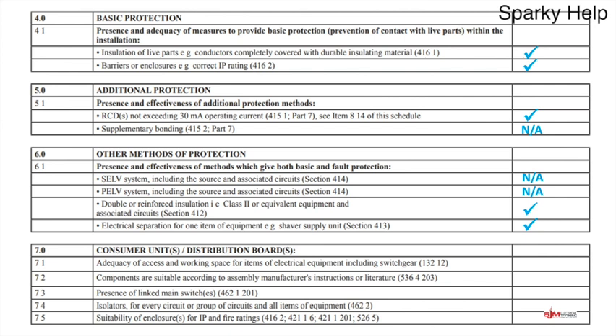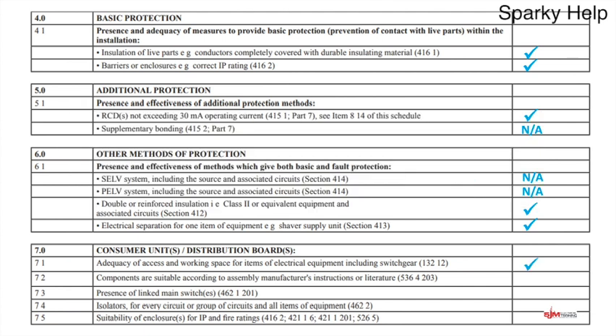The next one, we're looking at consumer units and distribution boards, adequacy of access and workspace for items of electrical equipment including switchgear. The regulations basically just say that wherever you put something you must have sufficient space for the initial installation and later replacement of individual items of electrical equipment, accessibility for operation, inspection, testing, fault detection, maintenance and repair. There are no measurements, you've just got to meet that. So you use your judgment. Have you still got it, or has someone built a wall in front of it? Wasn't there originally. So hopefully that would be a tick.